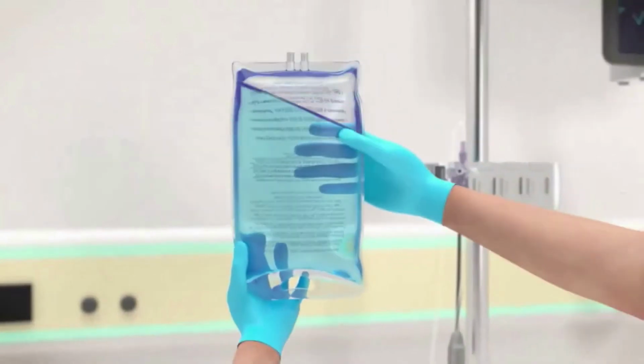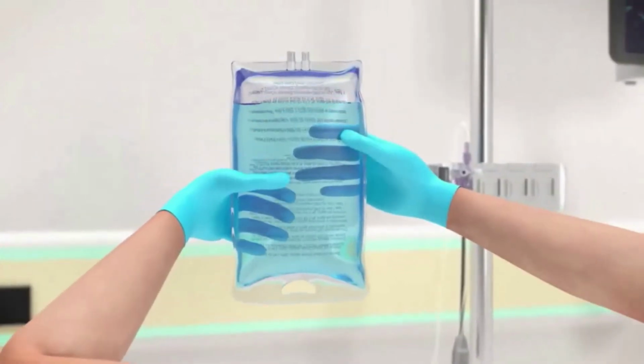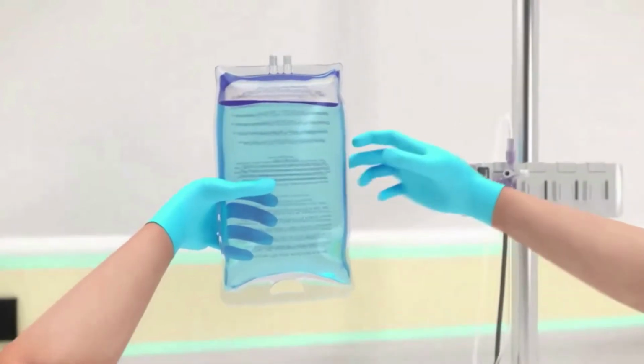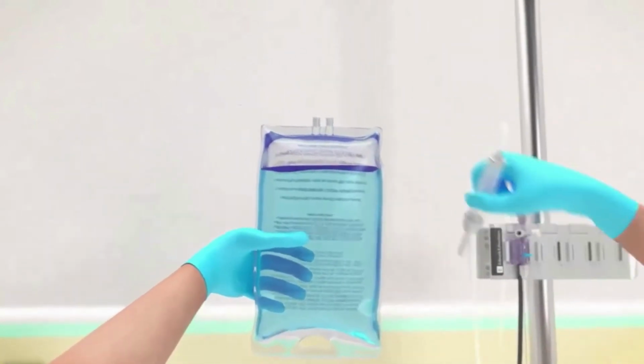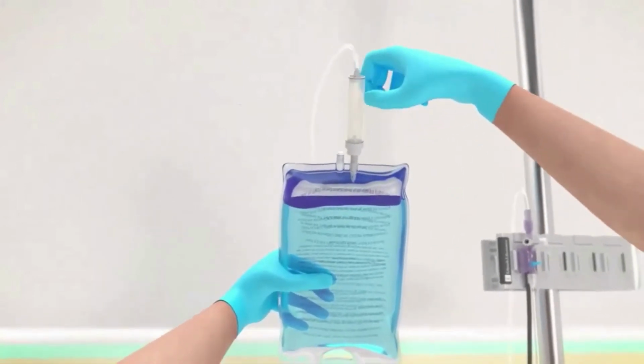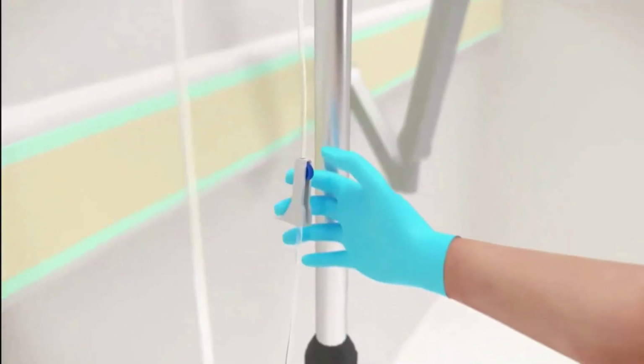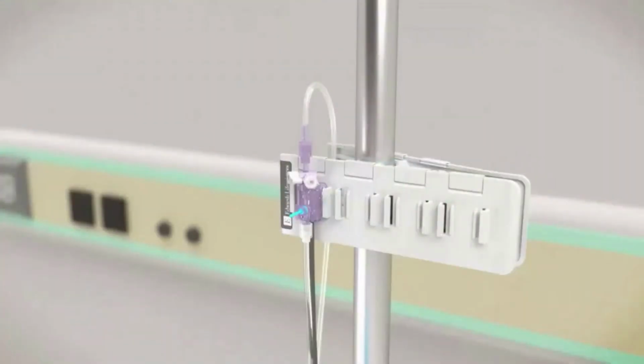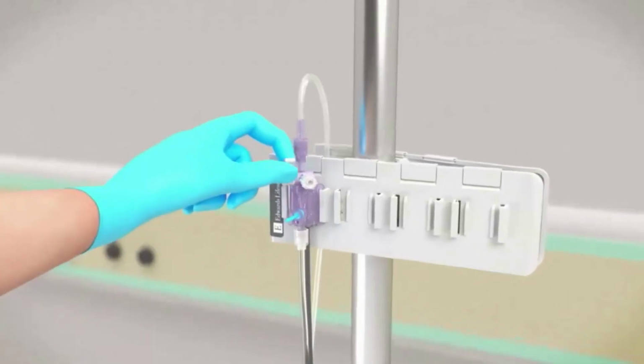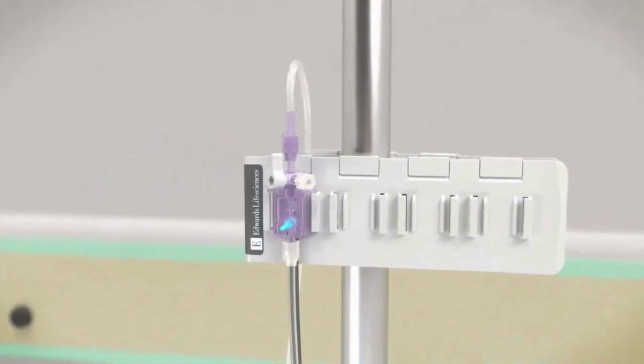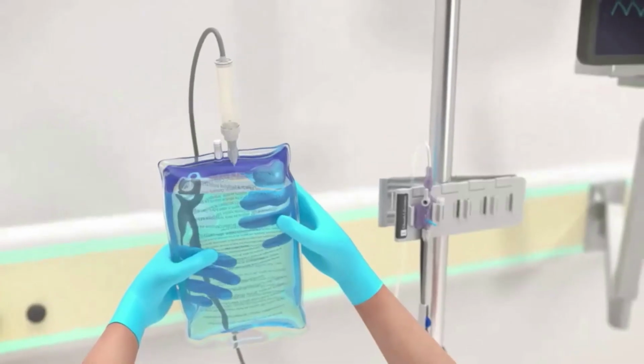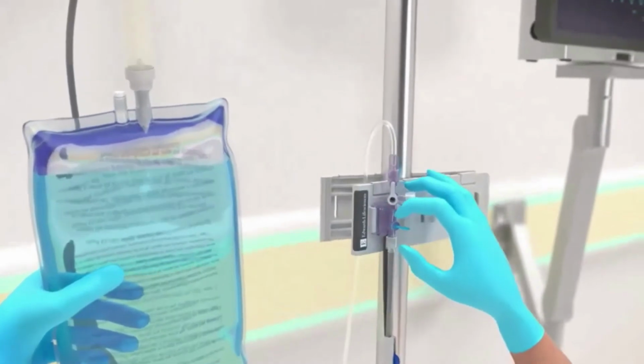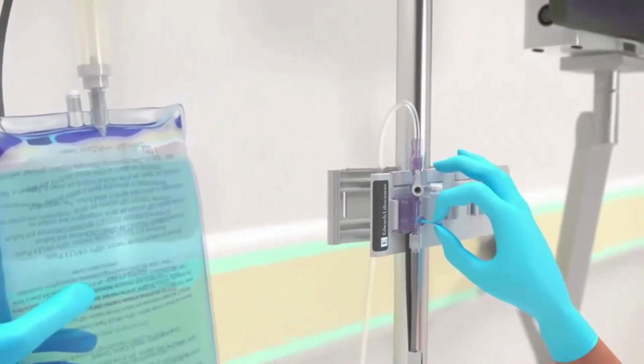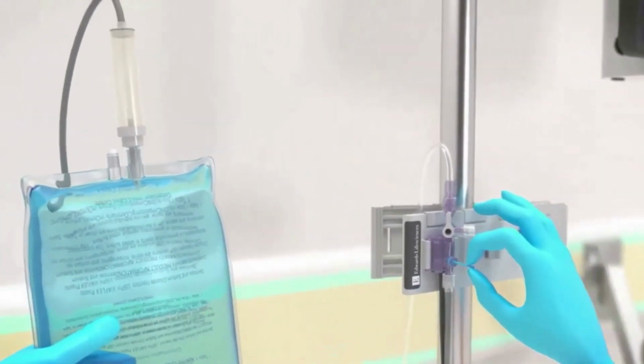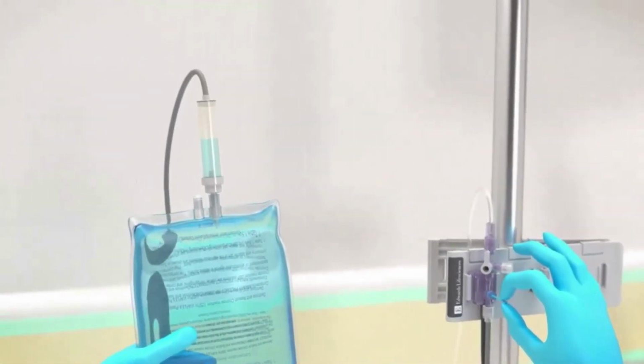Invert the normal saline IV bag so air rises to the base of the bag. Anticoagulation per institutional policy. Spike the IV bag with the fluid administration set, keeping the drip chamber upright. Open the roller clamp on the IV set. Open the vent port by turning the stopcock toward the patient's pressure tubing and away from the transducer while leaving the vented cap in place. While keeping the IV bag inverted, gently squeeze air out of the bag with one hand while pulling the snap tab flush device with the other hand until air is emptied from the IV bag and the drip chamber is filled at least halfway, or per institutional policy.